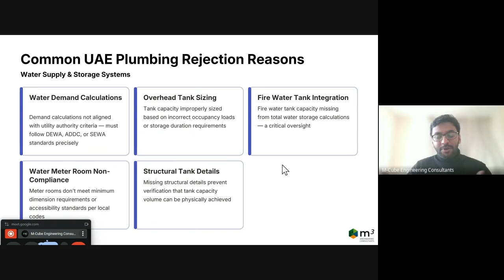When submitting water supply drawings, ensure you include structural tank details, since this relates to structural design. We give the tank capacity to the structural engineer, who must ensure the design is structurally sound, and this should be part of your drawing. This is when you know the total volume and the available freeboard. This is often missed, but in Sharjah, if you miss it, you won't get approval. You must show structural tank details in your water supply drawings in Sharjah, or else you'll get comments and need to resubmit. This may not be mandatory in Dubai, but it is in Sharjah.